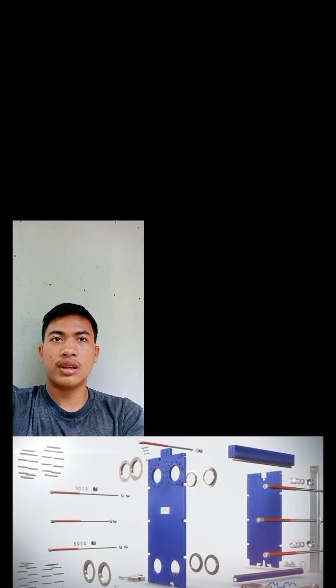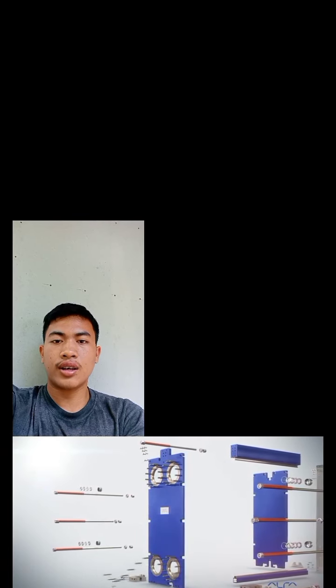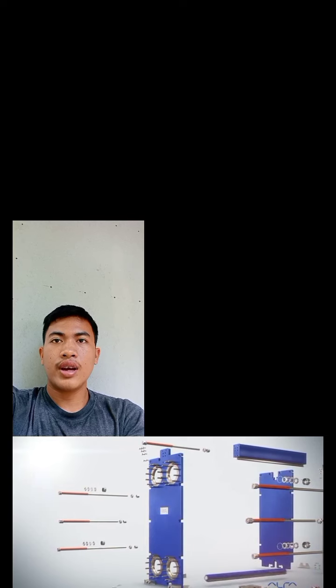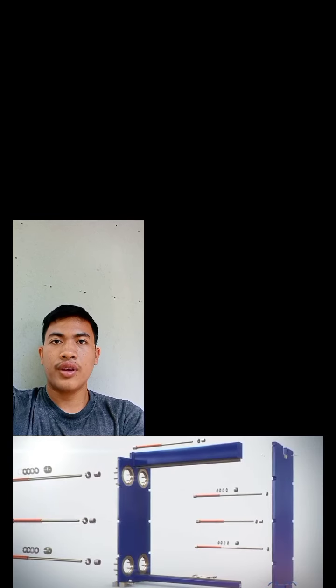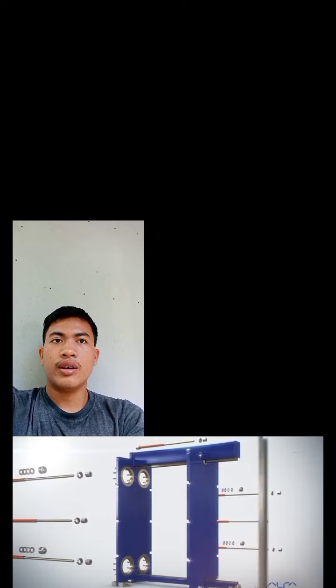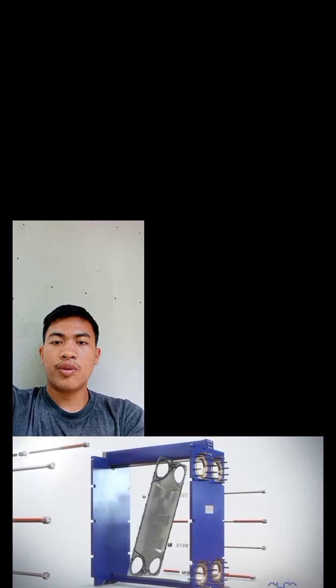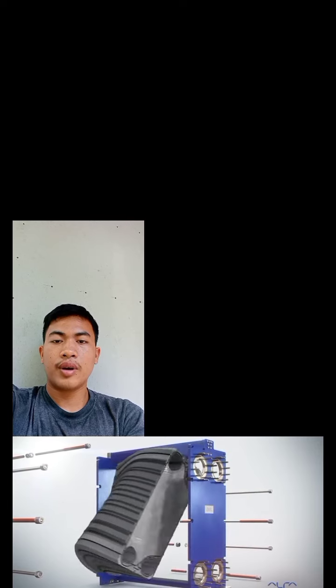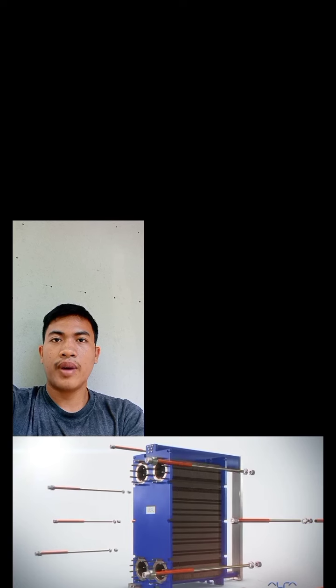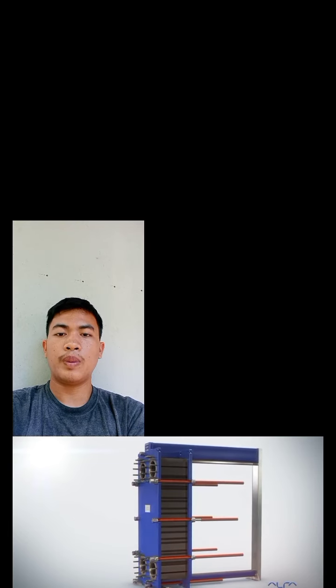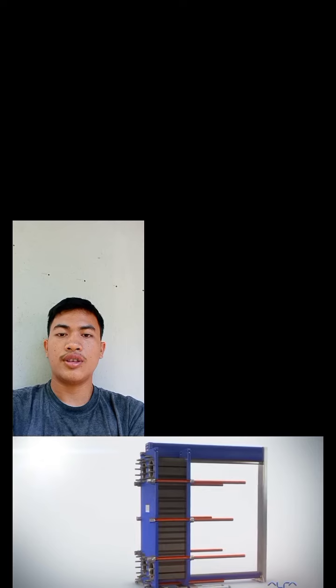Check all connections for possible leaks after the initial startup. If the heat exchanger fails to perform properly after startup, all air must be removed from the primary side, and install a backflow preventer on the primary input as overheat protection. And that is a simple plate type heat exchanger.